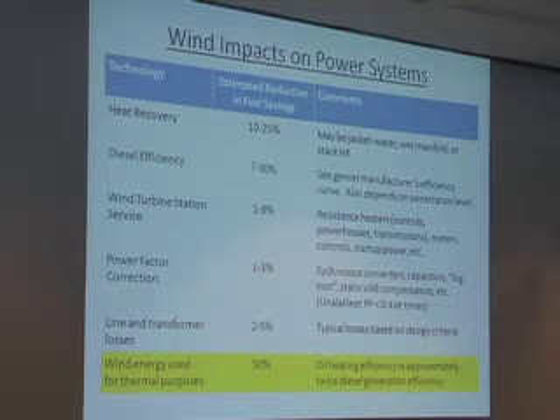Power factor correction. Often in these projects, there's a need for power factor correction. It can actually be exacerbated by high wind penetration. We've seen this in Unalakleet. There are some large induction motors at the fish processing plant there, and because the wind turbines produce unity power factor, and they're at times at fairly high penetration, as you've seen, we've seen power factors as low as 40%, and there's a risk of actually tripping the entire system offline if the diesel generator can't handle that.